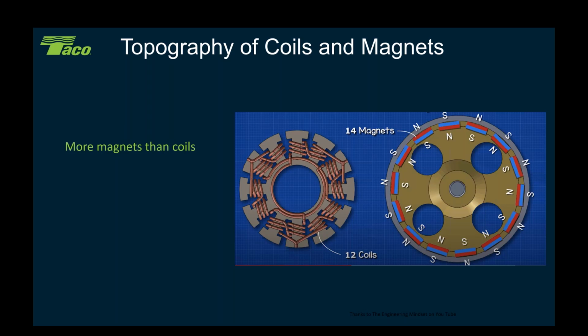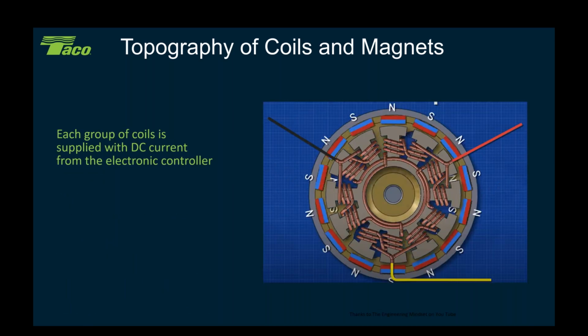Now, in an ECM motor, we always have more magnets than we have coils. That's to make sure we keep everything rotating. So each group of coils is supplied with DC current from the electronic controller. And this is really important to understand. If you look at the picture, you can see the 3 different sets of power connections: the red, the black, and the yellow. Those are each set of coils that are powered by DC power.